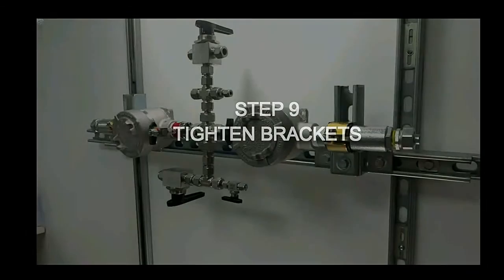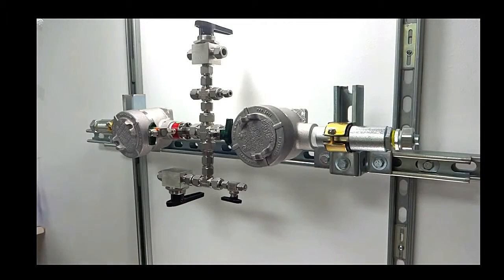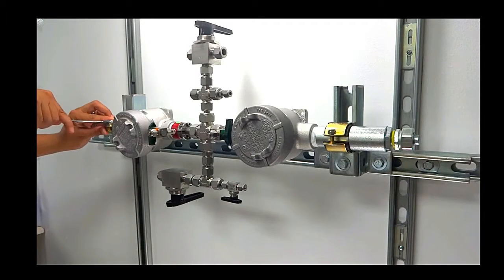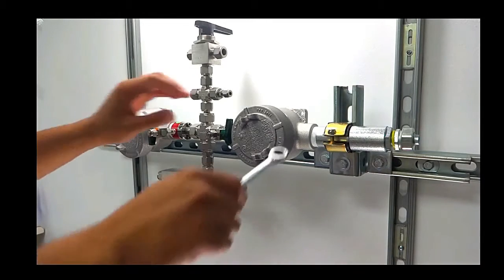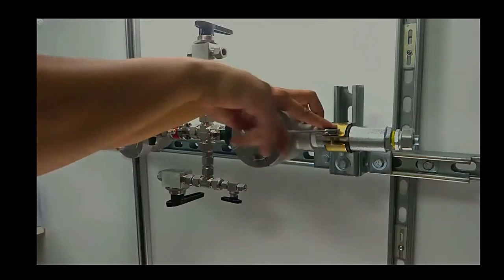Probes should be cleaned one side at a time. In order to clean the other probe, repeat steps 3 through 8, excluding step 4. Step 9. Tighten brackets. Once both sides of the probes have been cleaned, tighten brackets back to their original tightness. Once both brackets have been tightened, re-establish flow to the sample cell. Once flow has been re-established, it's very important that you check for any leaks.